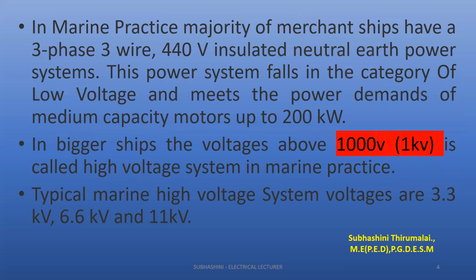In marine practice, the majority of merchant ships have a three-phase, three-wire, 440 volt insulated neutral power system. This power system falls in the category of low voltage and meets the power demand of medium capacity motors up to 200 kilowatts. For bigger ships, above 1000 volts is called an HV system in marine practice.